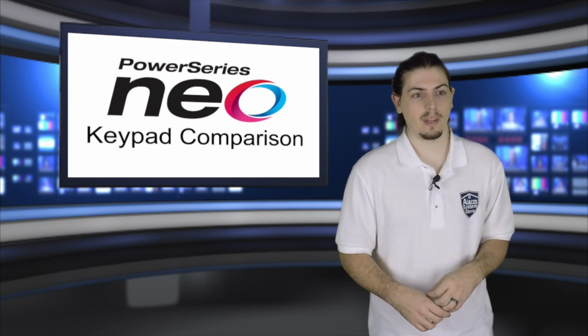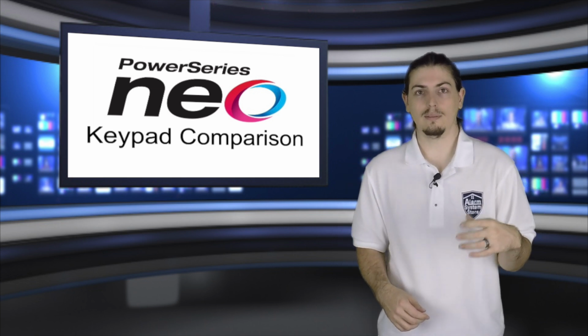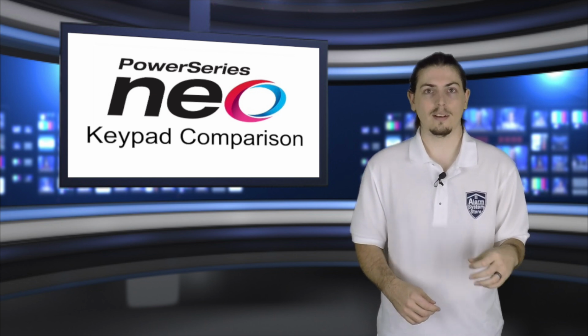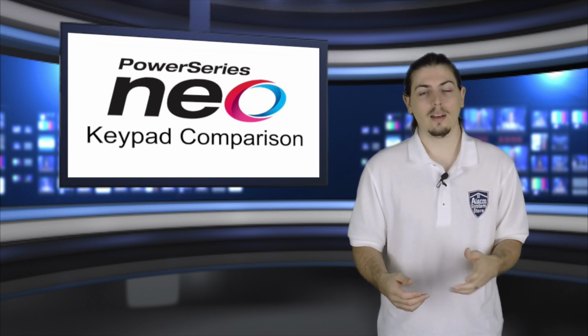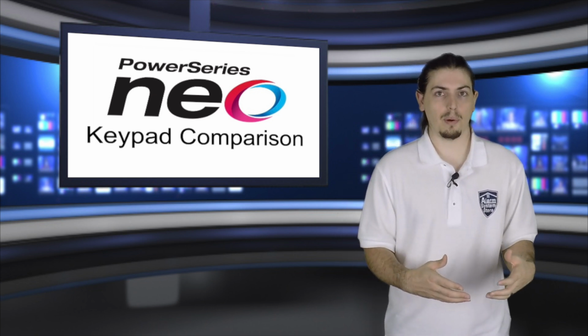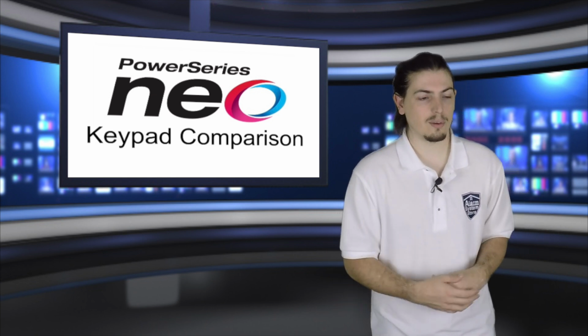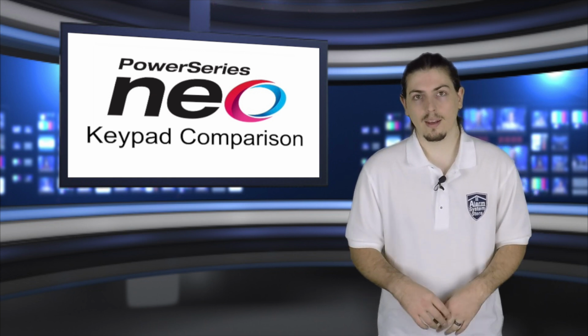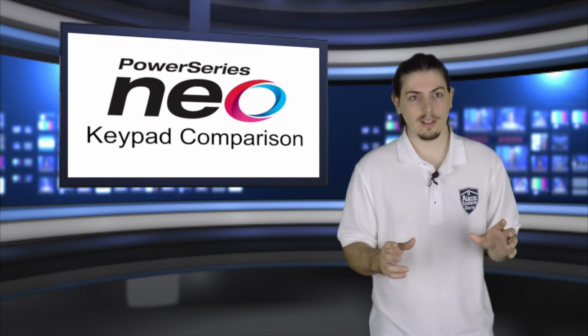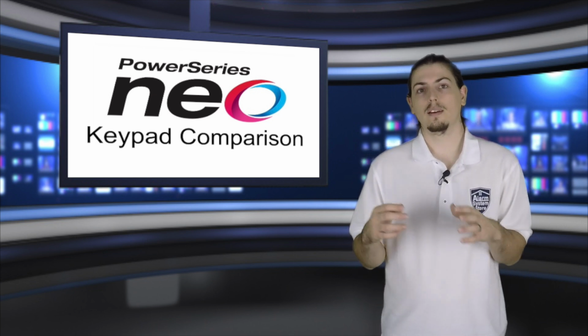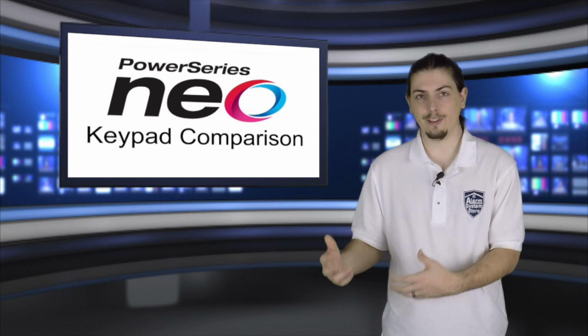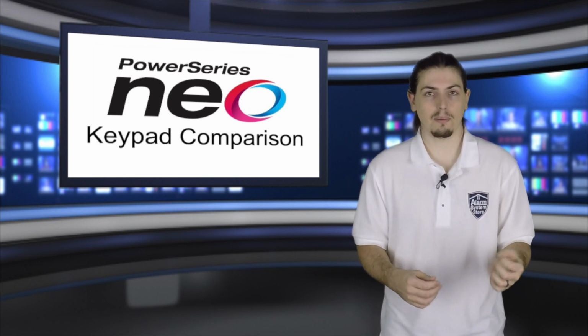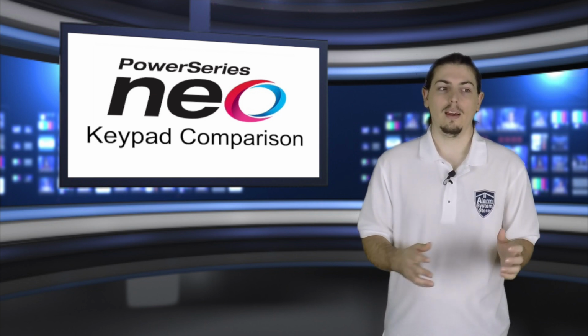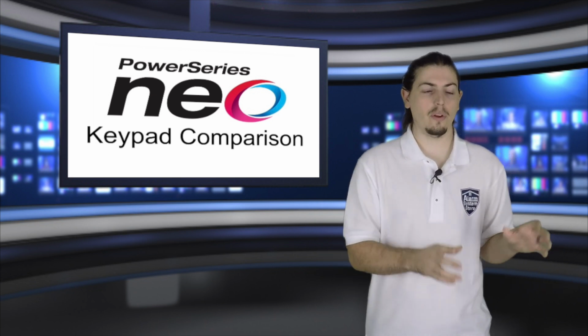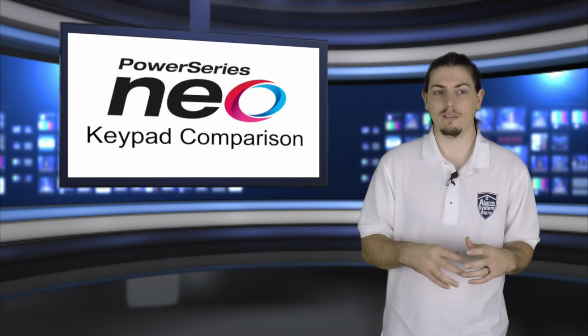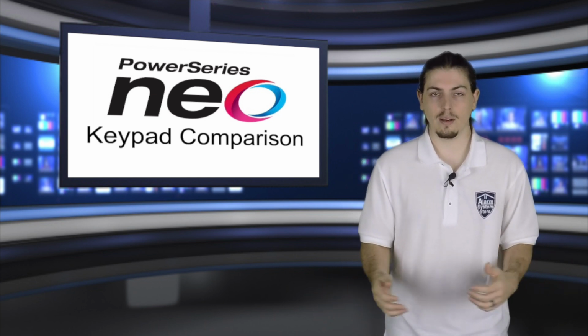So you might have HS2, which you can ignore, ICN, which is an icon keypad, RF. And so that means that that icon keypad has a PowerG transceiver built into it. Or you might see the HS2 LCD, which is the LCD keypad, full message display, WF, which is a wireless keypad, PV, which has prox tag support and voice prompting. And so once you know what the letters mean, you can figure out what any keypad has on it pretty easily.